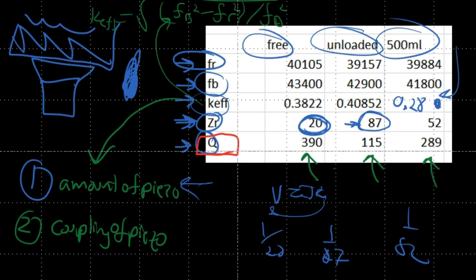So just because the coupling reduced doesn't mean that you don't have good coupling. It's just that you increase the amount of other stuff there. Therefore, you decrease the amount of coupling. But for example, if you move the piezoelectric discs off of the nodal point of the transducer, then the coupling would decrease and you wouldn't be adding any more material. So there's also that case where you can have less coupling and the same amount of material, same amount of piezo and the same amount of other stuff. So hope that all made sense.